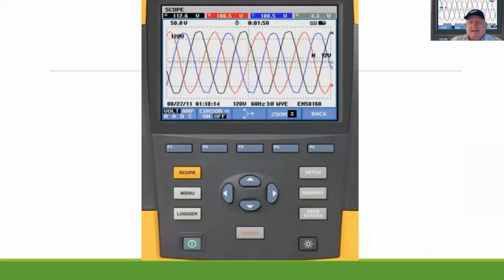So this device allows us to look at all three of those phases, look at all of the wave characteristics of A, B and C phase, and look at the quality of that power. It also gives us the average voltage between A to B, B to C, and A to C. It shows us that we have roughly a 4.3 voltage distortion. Well, that is roughly about 2%. That's not too much. That's not really a problem.